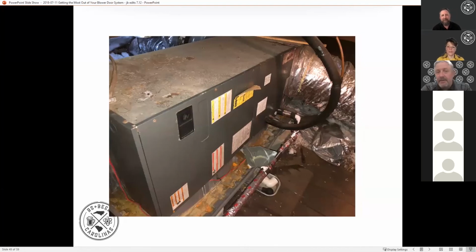There you can see the air handler. A lot of times a telltale sign of the interior condition is that secondary drain pan—you can see a lot of corrosion there. That tells you it's most likely a coil with two dissimilar metals starting to eat themselves up, and that rust coming out is just galvanic action taking place inside the air handler.